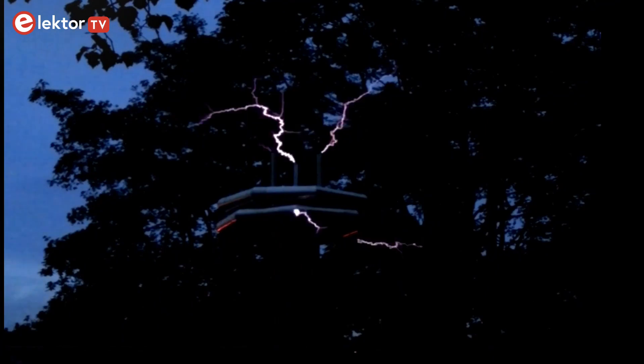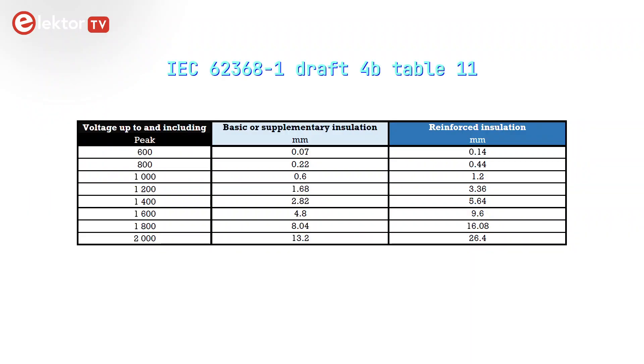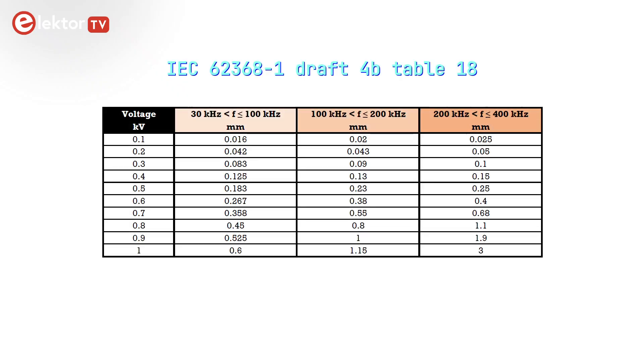Unfortunately this is not the complete story, as there is also a frequency component to be considered. Up to frequencies of 30 kHz the values I mentioned are probably okay. I haven't really figured out the frequency part, but my interpretation is that this is only an issue when the high-frequency working voltage has values of 1 kV or more. Table 11 in my draft document starts at 600 volts with a clearance of 0.14 mm. This value is much lower than the 1.5 mm clearance obtained from the up to 30 kHz table, and you must use the highest value. The same situation applies for creepage distance, suggesting that in my scenario I can ignore the frequency part.